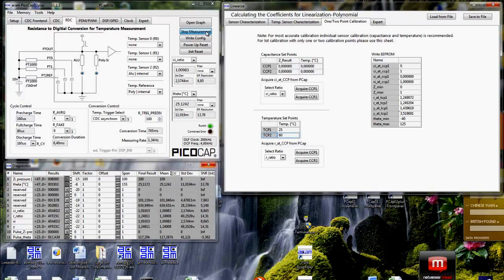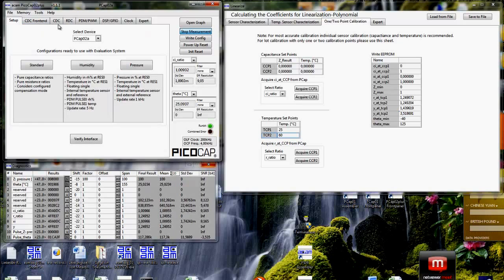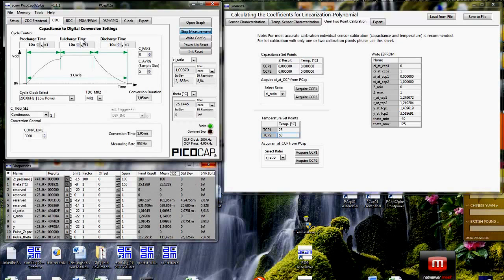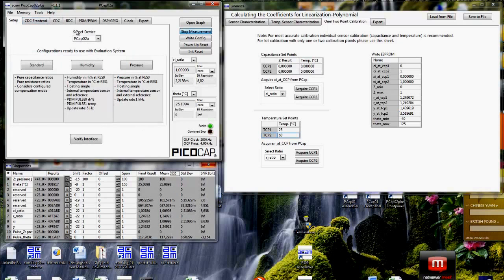One remark at the end, the general setup which was loaded with the project, or which can be loaded by using the pressure button here, is like a standard setting, which is a good starting point for most sensors. However, of course you can adapt all the parameters you like, for example the averaging rate, timing settings and so on, to your needs, and use that configuration to do the linearization or to generally run your sensor. Whatever you do, you can then at the end save the whole project. So if you close the software, you will be asked anyway, or you can alternatively say save project.